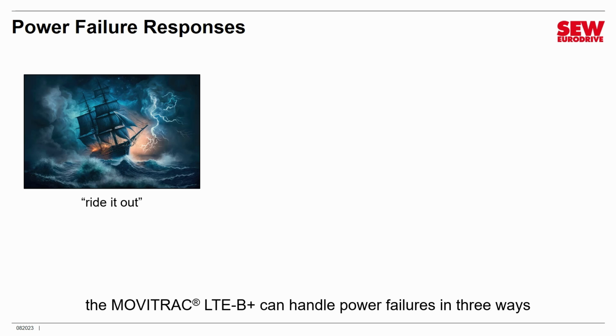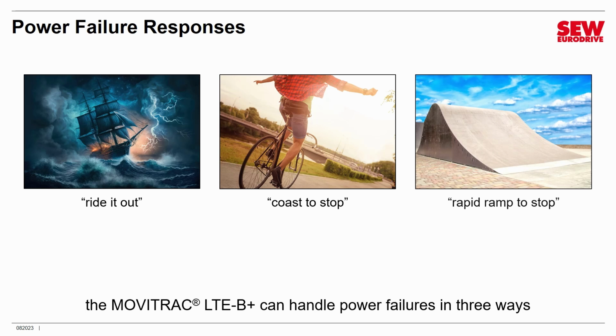As it turns out, there are actually 3 different ways that the MOVITRAC LTE-B Plus can handle this, and it's your choice which one it is. The first one is ride it out. In other words, don't do anything, just hope the power comes back in time before the capacitors go flat. The second one, which is similar to the way an ordinary stop is handled, is coast to a stop. In other words, shut the VFD output stage off and just let the motor coast. And then the third possibility is do a deliberate rapid ramp to a stop.